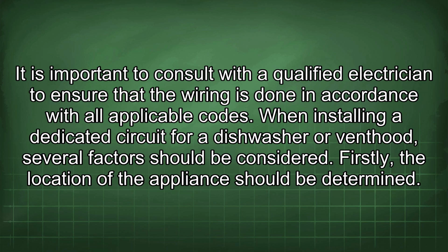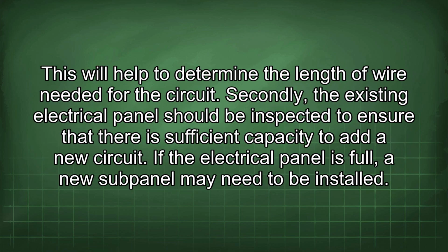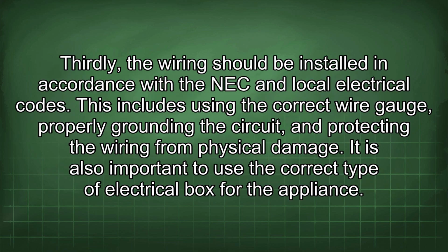When installing a dedicated circuit for a dishwasher or venthood, several factors should be considered. Firstly, the location of the appliance should be determined. This will help to determine the length of wire needed for the circuit. Secondly, the existing electrical panel should be inspected to ensure that there is sufficient capacity to add a new circuit. If the electrical panel is full, a new subpanel may need to be installed. Thirdly, the wiring should be installed in accordance with the NEC and local electrical codes. This includes using the correct wire gauge, properly grounding the circuit, and protecting the wiring from physical damage.